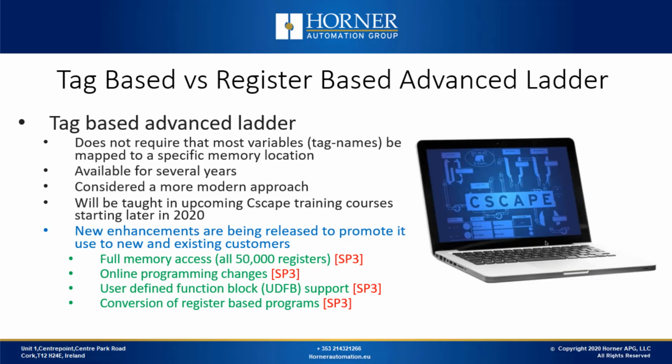You will also be able to make online programming changes, which is a method of making programming changes without stopping the controller. User-defined function blocks is a key feature that has been added in TagBased Logic, which we already have a full webinar explaining. The last enhancement is one that will be very important for those of you who have lots of pre-existing register-based libraries, as we are introducing the ability to convert your register-based projects over to new tag-based versions. This enhancement will come with Service Pack 4, which will be coming in the near future.